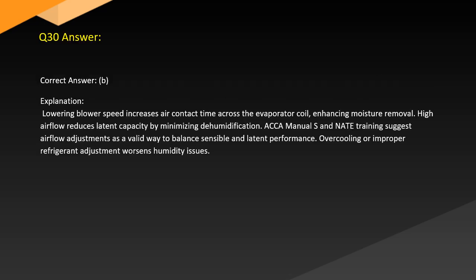Answer. Correct answer, B. Explanation. Lowering blower speed increases air contact time across the evaporator coil, enhancing moisture removal. High airflow reduces latent capacity by minimizing dehumidification. ACCA Manual S and NATE training suggest airflow adjustments as a valid way to balance sensible and latent performance. Overcooling or improper refrigerant adjustment worsens humidity issues.